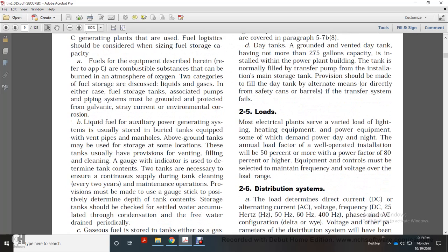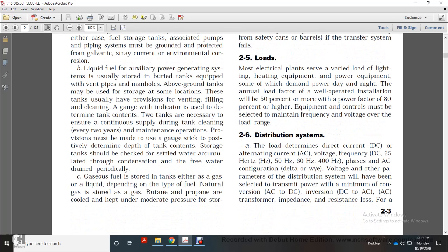Most electrical plants serve very varied loads — lighting, heating, and power equipment — some operating continuously day and night. The annual load factor of a well-operated installation will be 50 percent or more, with a power factor of 80 percent or higher. Equipment controls must be selected and maintained within frequency and voltage overload ranges. The distribution system load is determined by direct current or alternating current parameters — voltage, current, and frequency — including DC, 25 Hz, 50 Hz, 60 Hz, and 400 Hz.